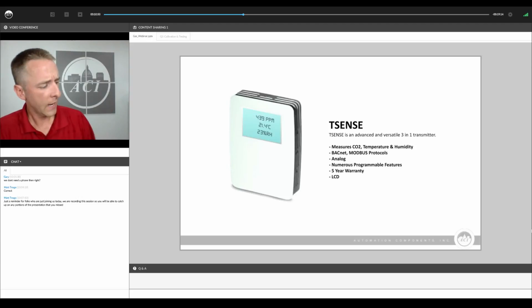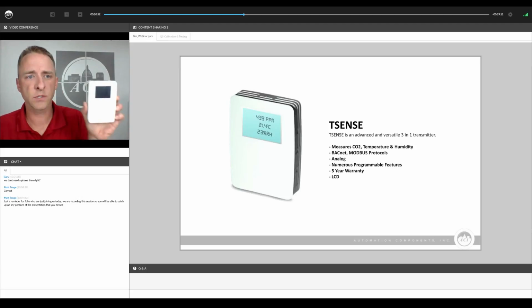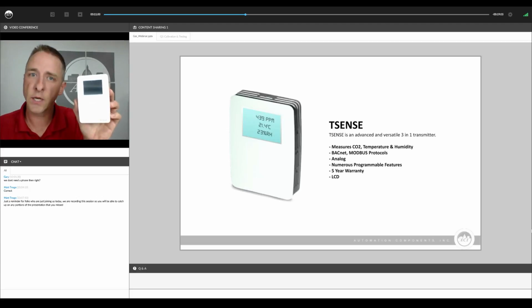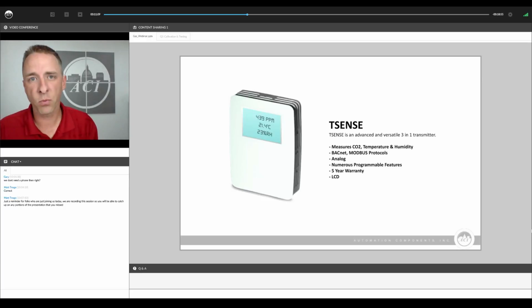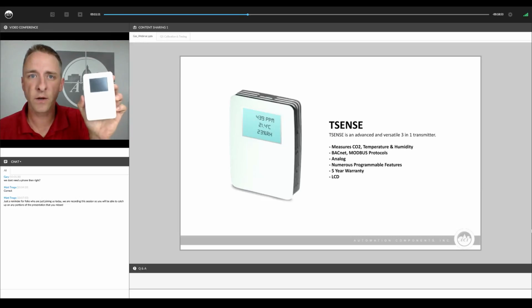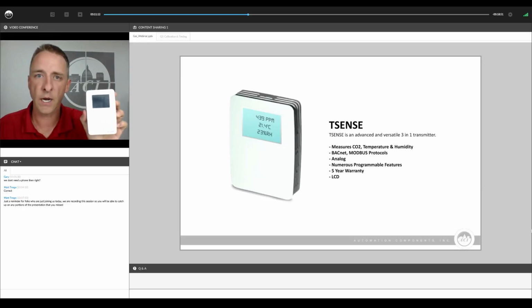We also have a new wall mount CO2 sensor that is a combination temperature, humidity, and CO2 in a sleek package with a touchscreen LCD. This is called our T-Sense, and it can give you an analog output for temp, humidity, and CO2, or a BACnet output with a number of user configurable features using the touchscreen right on the display.